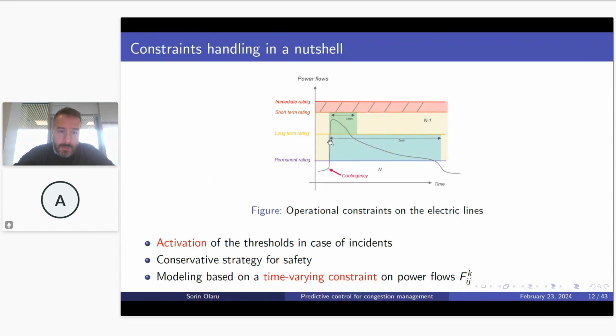If ever, due to an incident or an injection from one of those renewable farms, it happens that the power flow violates the permanent rating, then emergency control actions have to be taken in such a way that if the overshoot is higher than a certain long-term rating, then the control action has to be aggressive in order to bring back the power flow in 1 minute below this level, and then in 5 minutes to bring it back to the permanent rating.